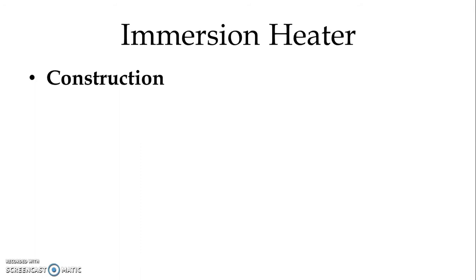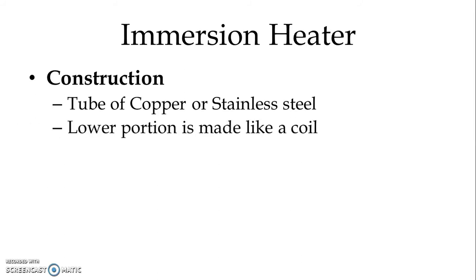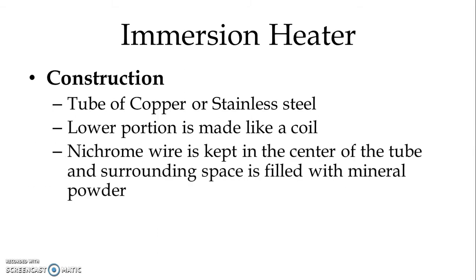If we see the construction, we have a tube that is made of either copper or stainless steel, and the lower portion of the tube is made like a coil. Nichrome wire is kept in the center of the tube, and the surrounding space is filled with mineral powder.